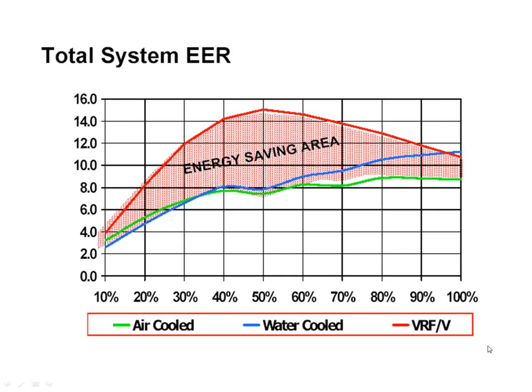All right, last couple of things here. We probably got about 5-10 minutes more stuff. The EER chart was actually put together by a VRF manufacturer, not one of the ones we rep at our office, another one, but they made this chart to compare air-cooled chillers, water-cooled chillers, and VRF. And you'll notice that on their chart, VRF always wins, right? Because they're a VRF manufacturer.